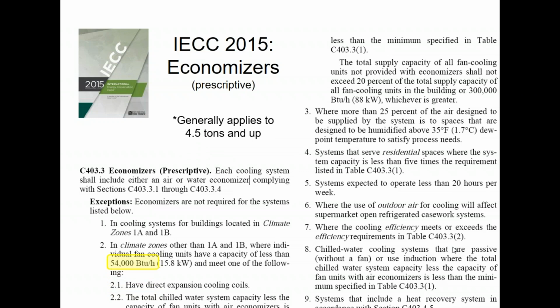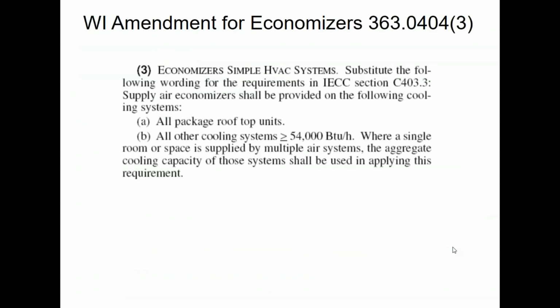Number 3, if you've got certain process things with humidity, fine, exception. Number 5, if you have a church that barely has any operating hours, fine, you can get an exception. Number 8, if you have chilled beams or something, you could probably get an exception. But your normal school, retail, office, those kinds of places, 5 tons and over, you're going to be using an economizer. That's per IECC. Wisconsin, if you guys are from Wisconsin, there's an amendment to that.